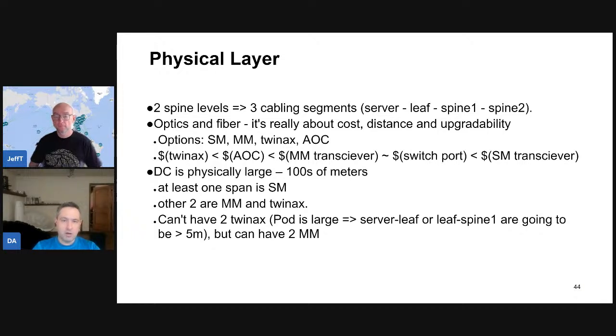Looking into the near or midterm future, it looks like the distance we can go with multi-mode optics is going to shrink further. So probably instead of what we are doing now, intermediate length segments with multi-mode optics and really long segments with single mode optics, they're probably going to be both single mode. Because for 800 gigs, multi-mode reachability is on the order of dozens of meters.